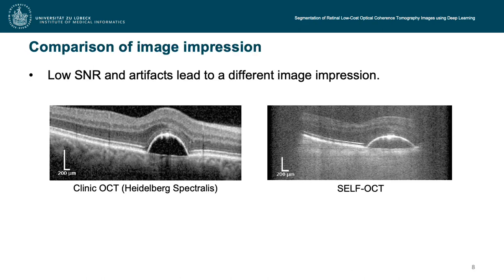Now we will look at the visual impression of the SELF-OCT in comparison to a clinical OCT. On the left you can see a B-scan of a Heidelberg Spectralis OCT and on the right a B-scan of the SELF-OCT of the same AMD patient. Comparing both scans, one notices the significantly different image impression. Due to the very cost-effective and compact optical design, images of the SELF-OCT show a lower signal-to-noise ratio and specific artifacts.